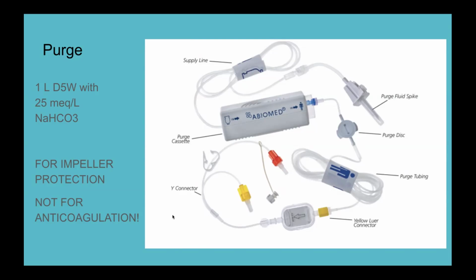So this purge protects the Impella. It is not meant to do anything specifically for the patient. It's to protect the device. And it's going to be very important that you ensure that the purge remains continuous and that there are no alarms associated with it perioperatively, as purge-related issues can lead to pump failure.